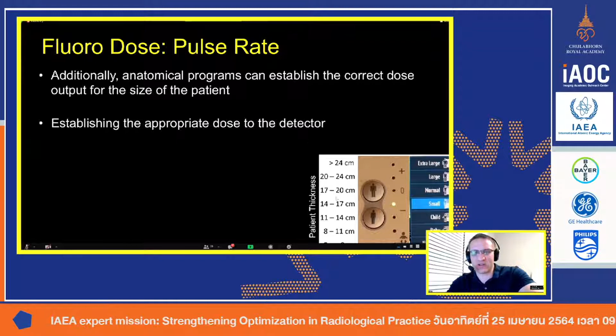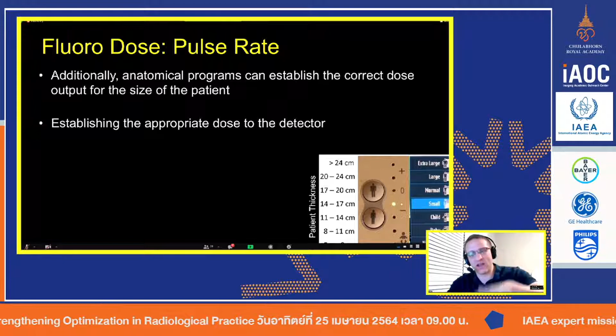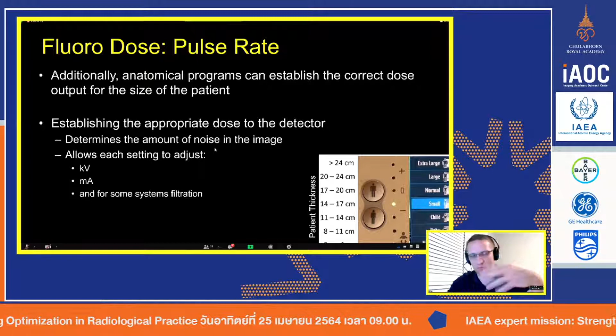And so we set it up so that the dose to the detector goes from small to large. You need to make sure you keep the right dose to the detector as the patient gets bigger and bigger. Remember, the dose of the detector determines the noise in the image. And it also allows the system to pick the right kV and the mA and the right filter for the procedure. So if you don't have the right dose to the detector, then all of these settings aren't going to be right. The image quality won't look right. The contrast will be a little off, and you may be even noisier as you get to bigger patients.